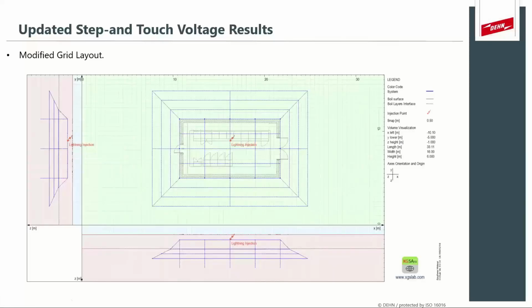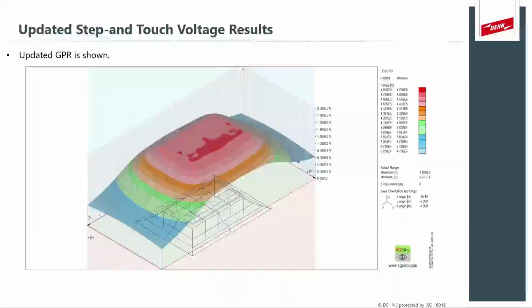Now, if we inject the same 50 kA into our new grid for very high frequency, you can see that we've suddenly established our equipotential plane. So there are not a lot of big differences in voltages on this graph that can cause step voltages.